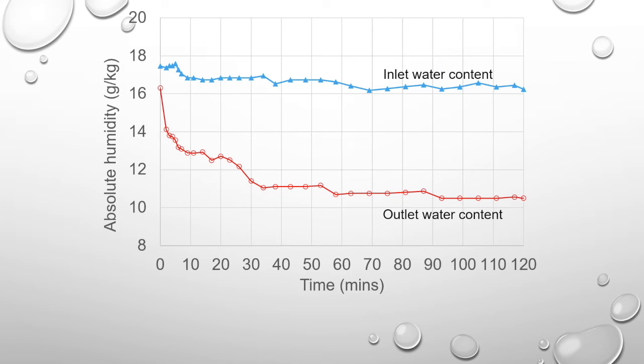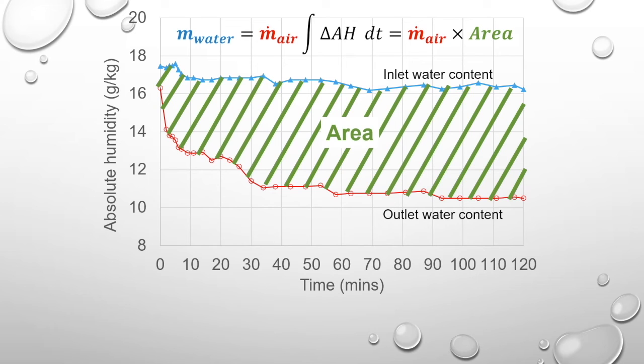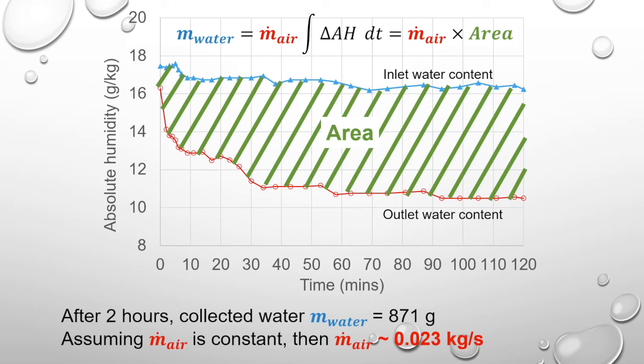Since we have measured the exact conditions of the inlet and outlet of the dehumidifier with respect to time, we can actually estimate the air flow rate based on the amount of water collected and the difference in absolute humidity of the inlet and the outlet, that is, the area between the curves. Assuming that the air flow rate is constant throughout the experiment, we can estimate it to be about 0.023 kg per second.